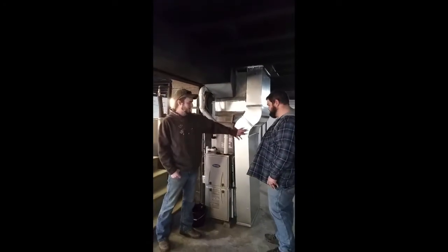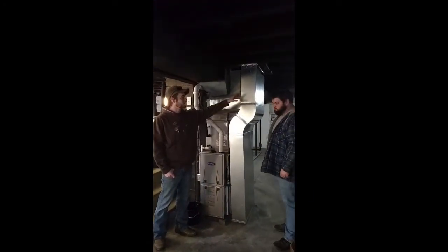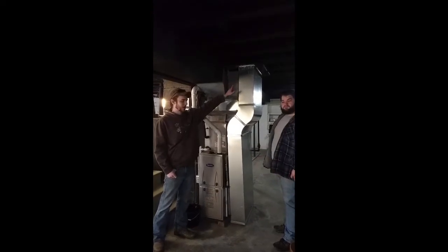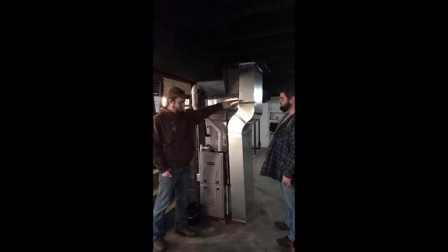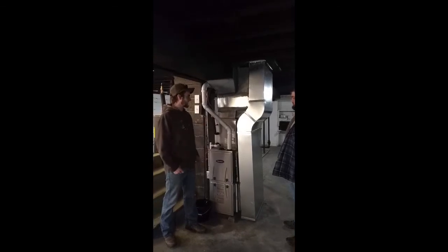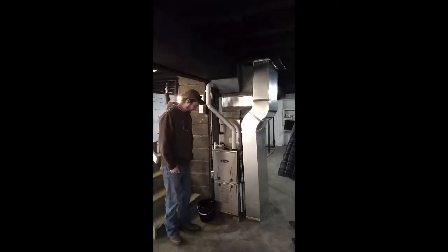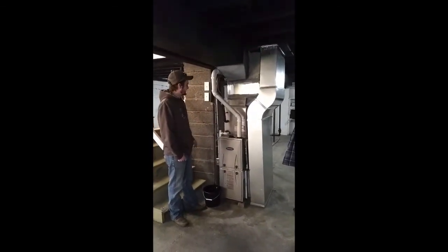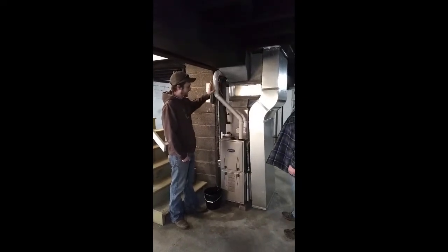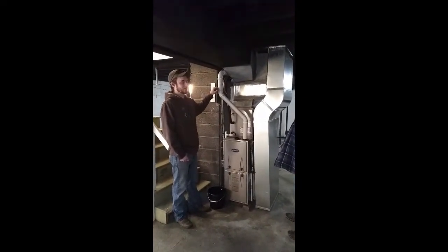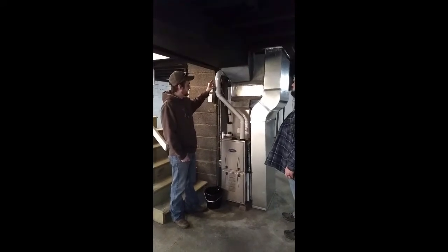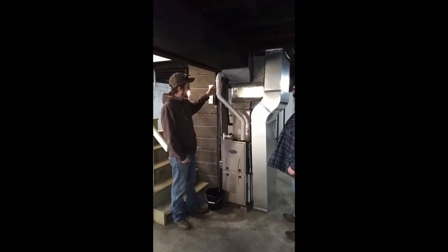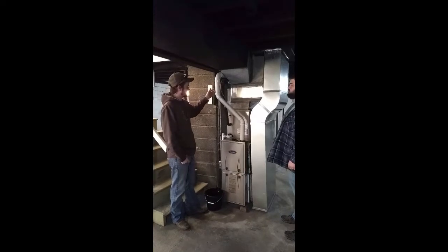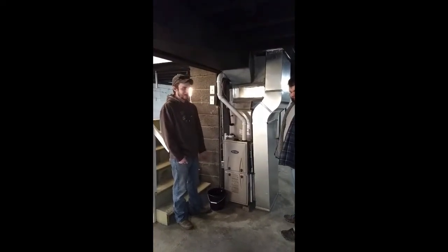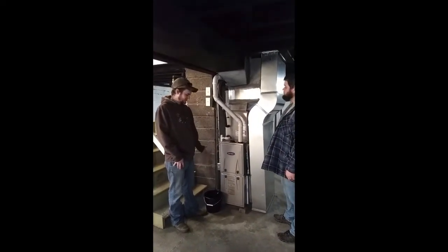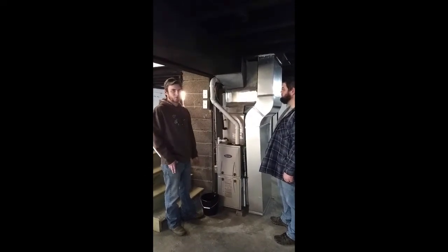It also has the return air right here, which is pulled directly from upstairs in the center of the house. So it's getting warm air to try to reheat it and keep the house warm. You also see this bucket, and it's actually catching water from my exhaust because it's burning very efficient currently, and I'm getting condensation quite a bit, and I just happen to have a small seep here, and it comes down and just drips in the bucket. I empty it about once a day, and it probably has about a half gallon of water in it.